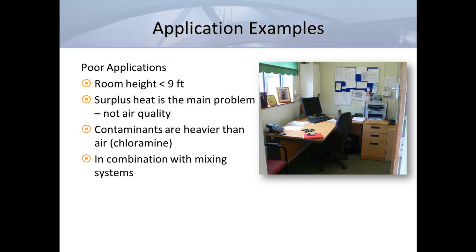In situations where contaminants are heavier than air, displacement would also be a poor choice. This could include indoor swimming facilities where chloramine could be a problem. In a chemical laboratory, displacement could result in spilled chemical agents being brought up from the floor to the breathing level. And last but not least, displacement ventilation should not be used in conjunction with mixed air products to serve the same space, as mixed air products would likely prevent stratification from forming correctly in the room.